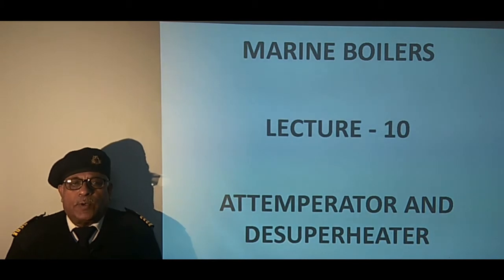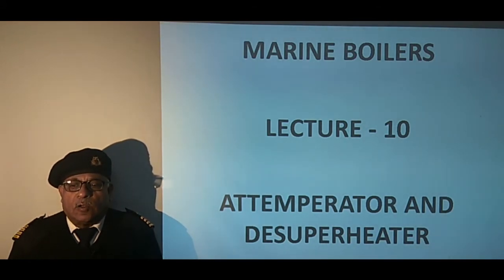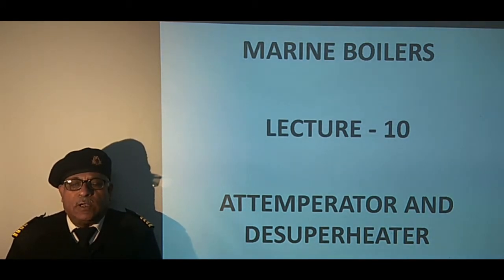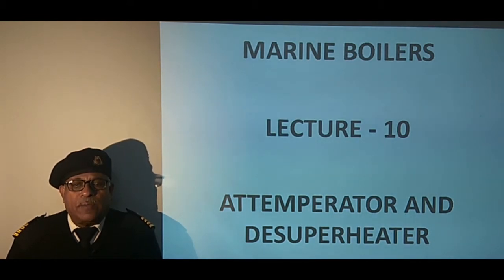Attemperators and De-Superheaters are both used to reduce the degree of superheat, but their purposes are different in each case. Attemperators are used to control the final degree of superheat so that steam temperature does not exceed the design value, which can result in failure of the superheater. Attemperators are installed between primary and secondary superheaters.